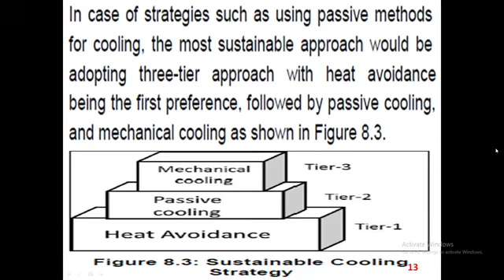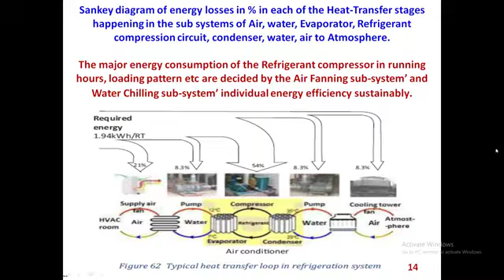So if you take any air conditioner, let us say around 2 kilowatt per ton it takes for the running ton, the supply air fan and the air handling circuits consume around 21%. Then the pump consumes around 8%. Then the HVAC compressor consumes around 54%. And the primary and secondary pumps consume around 8%, and the cooling tower consumes around 8%. This is where, like the Pareto principle, if the small subsystems are operated smoothly and efficiently, the compressor run hours can also come down. Each and every industry or building management system is working on how to reduce the compressor run hours, and how to make the compressor load efficiently during those run hours.